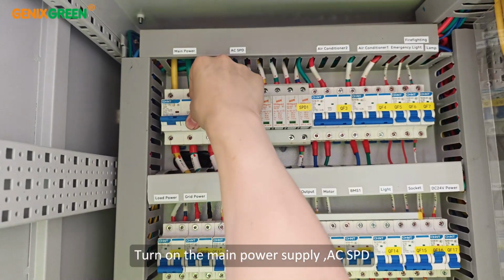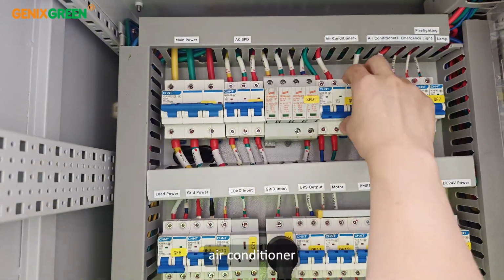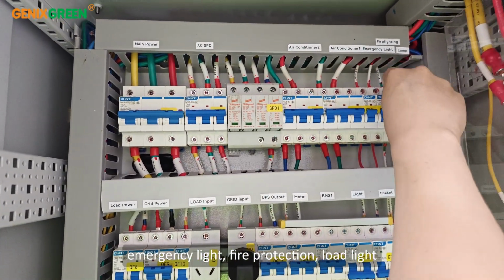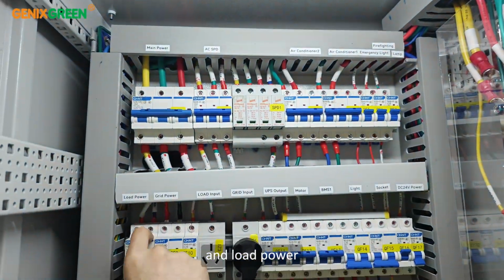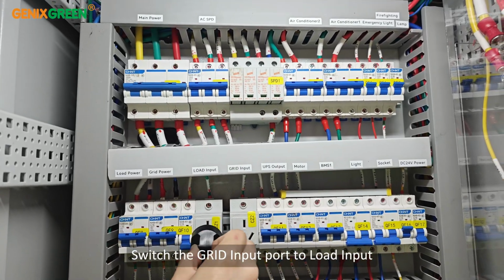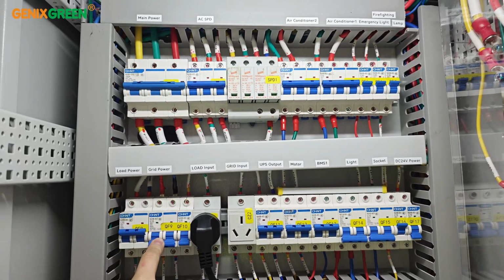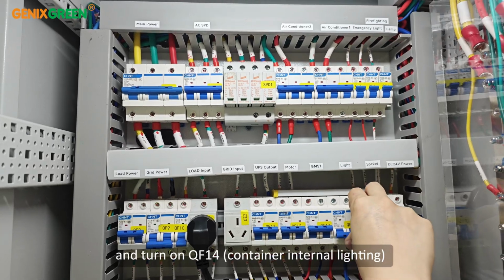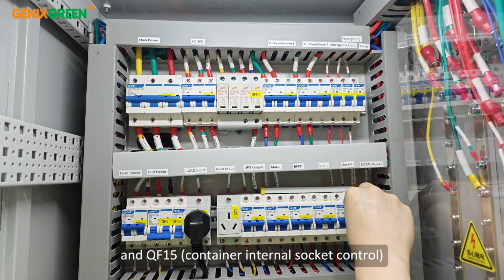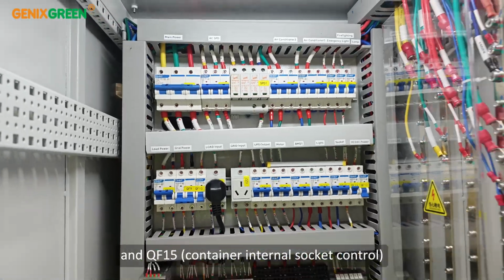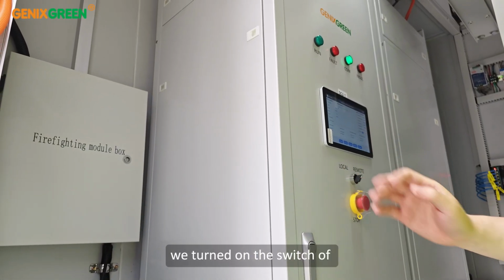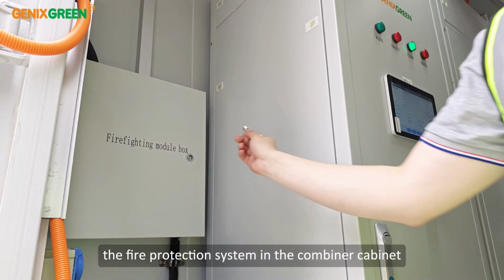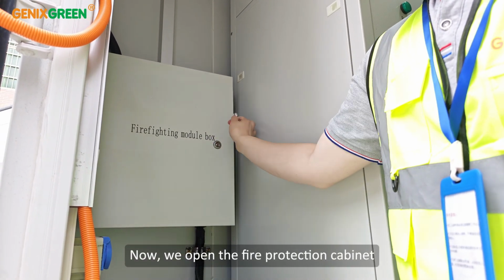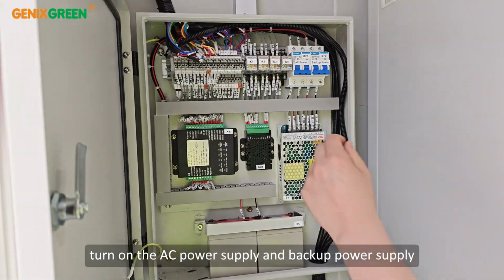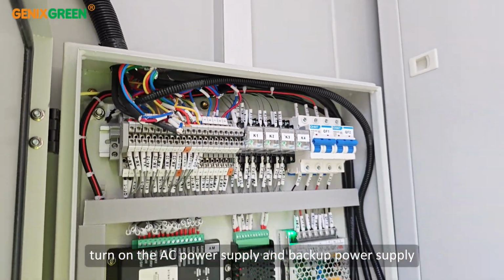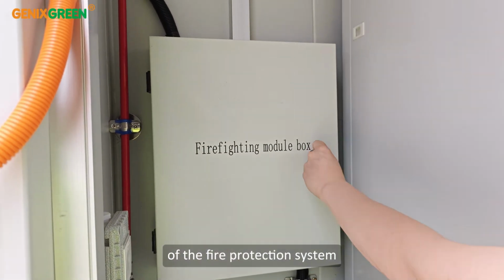Turn on the main power supply, AC SPD, air conditioner, emergency light, fire protection, load light, and load power. Switch the UPS input port to load input. Turn off grid power, and turn on QF14, container internal lighting, and QF15, container internal socket control. Just now, we turned on the switch of the fire protection system in the combiner cabinet. Now, we open the fire protection cabinet, turn on the AC power supply and backup power supply to complete the power on work of the fire protection system.